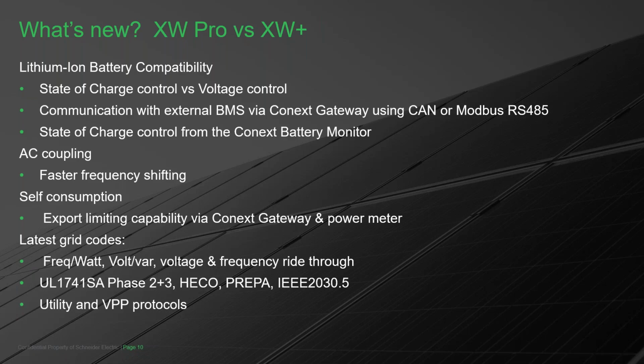AC coupling, what we have done here is we have sped up how quickly our frequency shift acts. So basically not to hit the batteries with such a high current. So there's not any issues there. Self-consumption, we have a meter now that allows you to sell back to the main panel and not sell to the grid in places where it's not allowed.